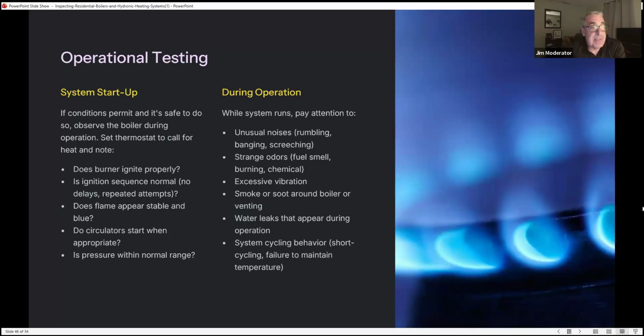If conditions permit and it's safe to do so, observe the boiler during operation. Set the thermostat to call for heat. That's kind of obvious. Does it start? Does it shut off? Is the flame stable? We've been all through this. During operation, you want to pay attention to unusual noises, strange odors, excessive vibration, smoke or soot around the boiler, water leaks, and system cycling behavior, short cycling, failure to maintain temperature.